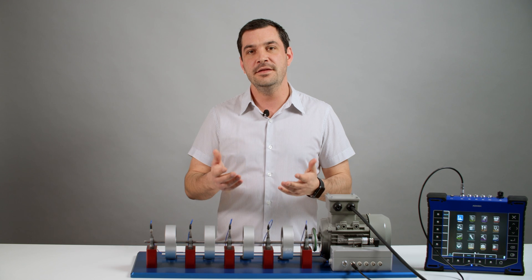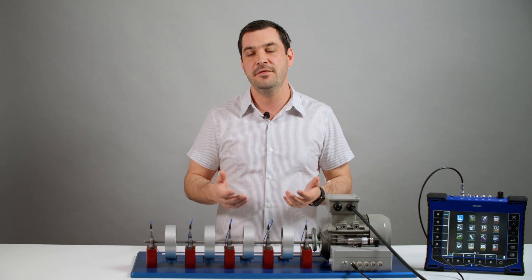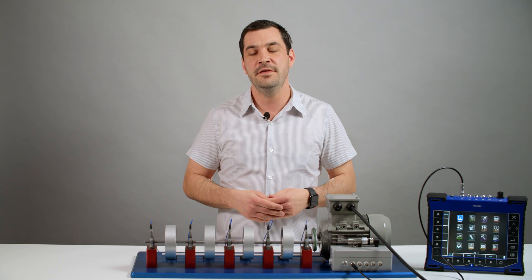Now you even don't need any vibration meter. Your smartphone has acceleration sensors already and we are using them for taking the readings during balancing job. This is probably the first app capable of that. Let us know in comments if we are wrong.